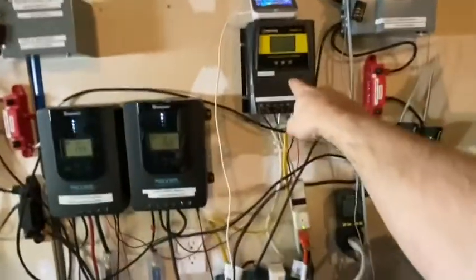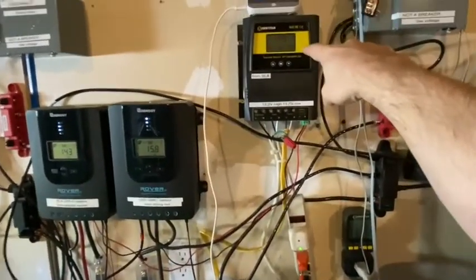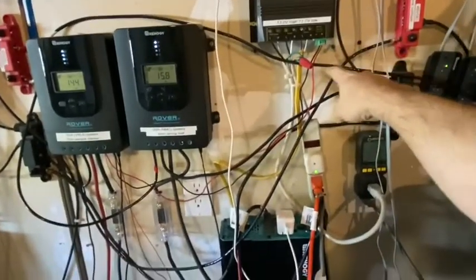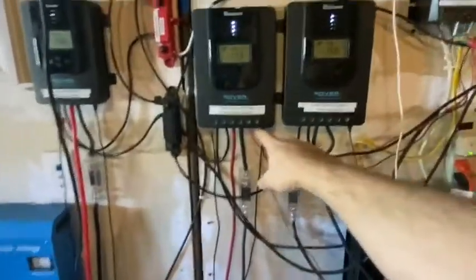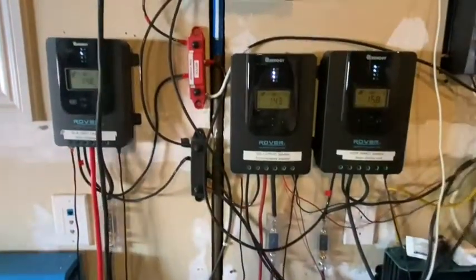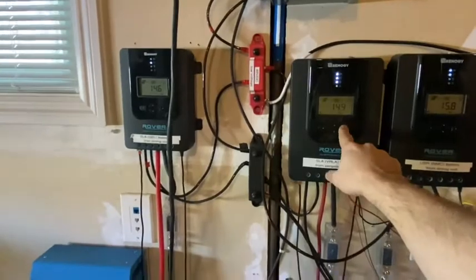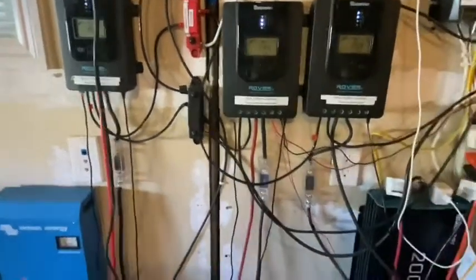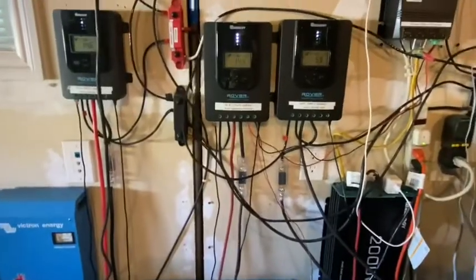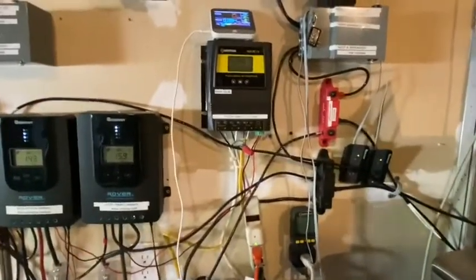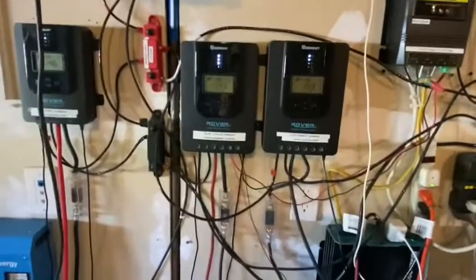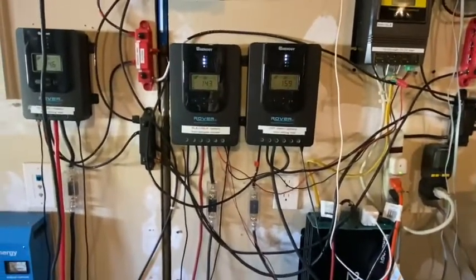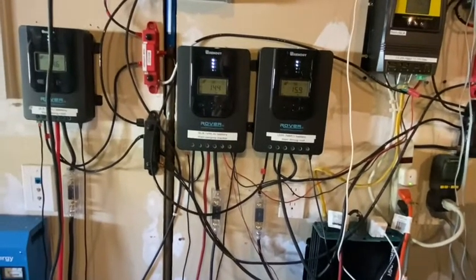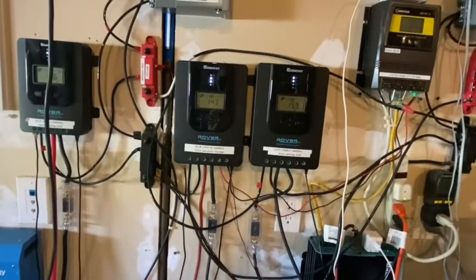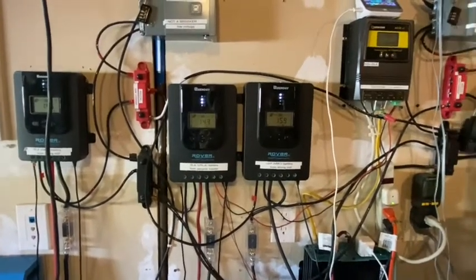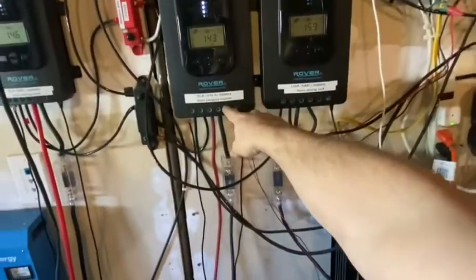So there's the Spartan automatic transfer switch, currently running off batteries. I'm using the sense lines to read the output from this Renogy, and I can turn it off and on from the load on the Renogy. So I'm using the load off the Renogy as the voltage input sense on the Spartan. It's not running anything else. I find the Renogy output load useful in that way, but I do not see it as useful for running any real loads. It's more just for running the voltage sense circuits, because that's basically the output of the battery.